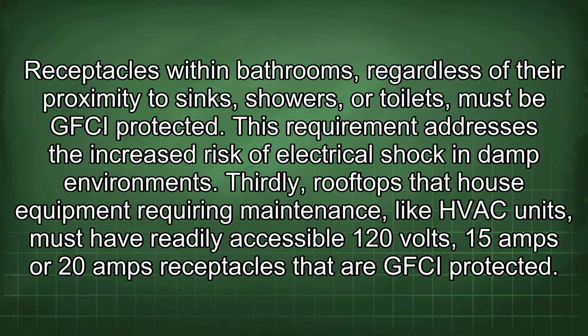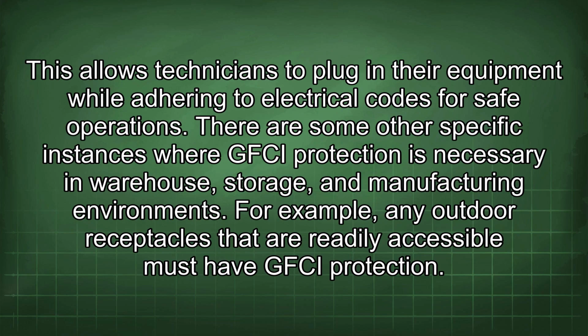Thirdly, rooftops that house equipment requiring maintenance, like HVAC units, must have readily accessible 120 volt, 15 amp or 20 amp receptacles that are GFCI protected. This allows technicians to plug in their equipment while adhering to electrical codes for safe operations. There are some other specific instances where GFCI protection is necessary in warehouse, storage, and manufacturing environments.